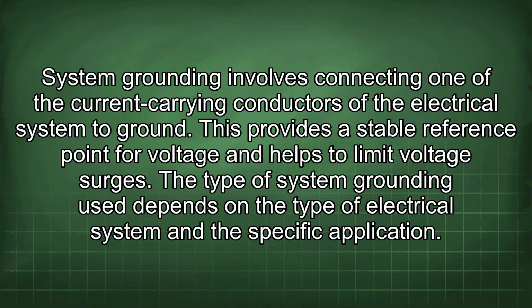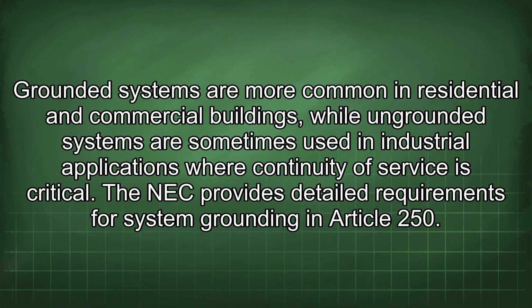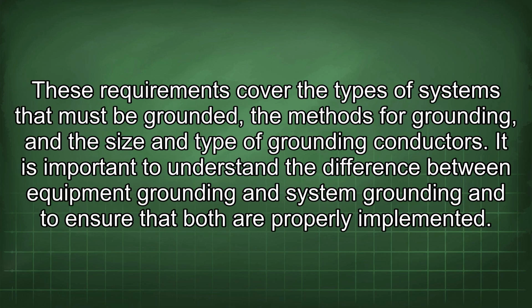The type of system grounding used depends on the type of electrical system and the specific application. Grounded systems are more common in residential and commercial buildings, while ungrounded systems are sometimes used in industrial applications where continuity of service is critical. The NEC provides detailed requirements for system grounding in Article 250. These requirements cover the types of systems that must be grounded, the methods for grounding, and the size and type of grounding conductors.